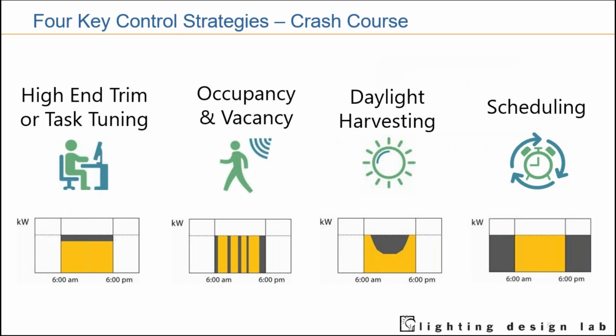So, a very brief review of four key control strategies for network lighting control systems. Let's start with high-end trim, also known as task tuning. That is the ability to put a ceiling cap on the output of luminaires. More often than not, and it's a good way to do it, designers and specifiers will be conservative and over-specify the lumen package of fixtures. This is done because they don't know if a space will be value engineered, if there are going to be darker colors on the walls, floors or ceilings, or if the room is going to get very dirty very quickly. For these and other factors, they may just over-specify the lumen package. And the high-end trim strategy is a great way to put a ceiling on the maximum amount of light a luminaire can produce, and that does a couple of great things.